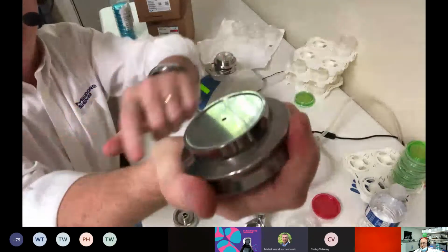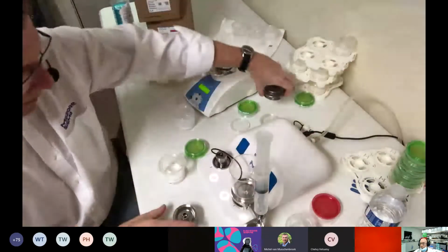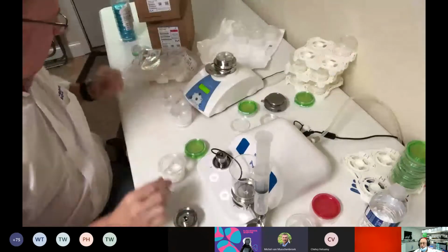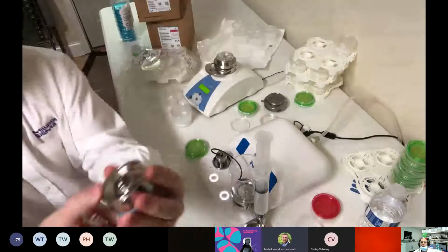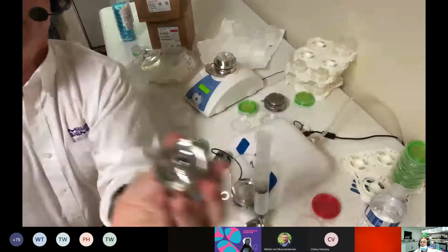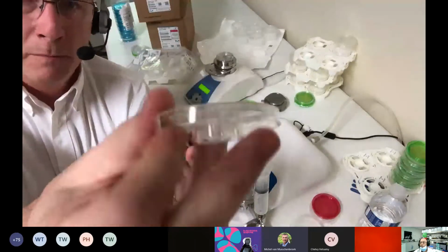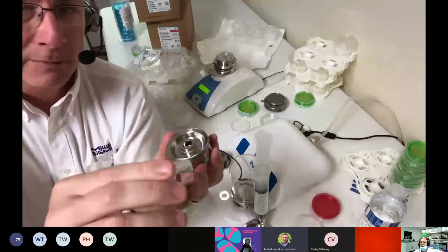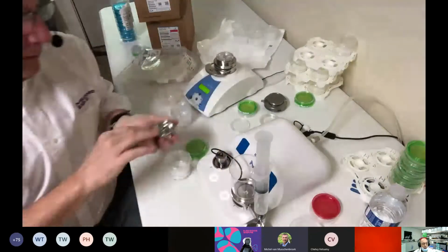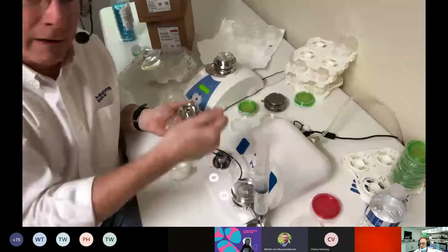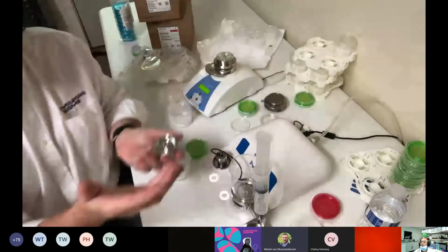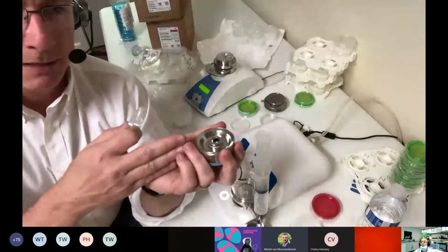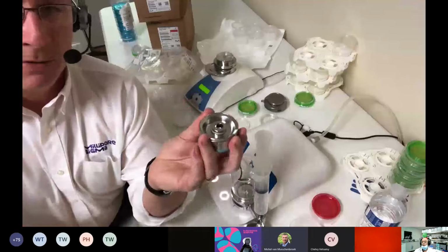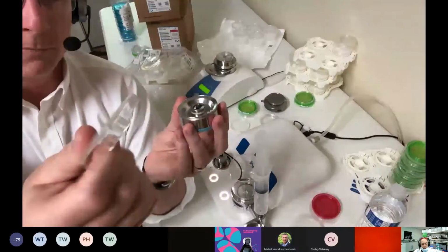What is different is that if you look at the old pump head, you know that it was flat, and you'd put that membrane separator and the unit would go on. The new units are, as you can see, quite different. One of the reasons is that we updated the funnel support, the membrane support, so that you didn't have to transfer. Now you don't need forceps at all. We had some people that would take the membrane support and transfer it over by forceps, and some people would turn the unit upside down and put it on. There was irregularity, and we wanted to make it easier to train people and make it consistent from person to person. So in doing that, we were able to create the system.